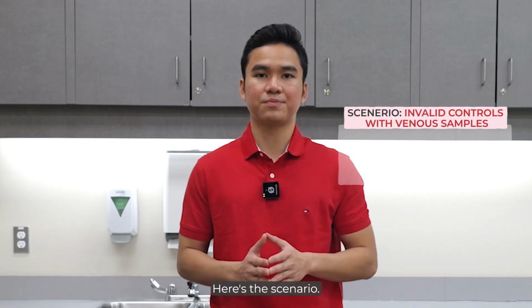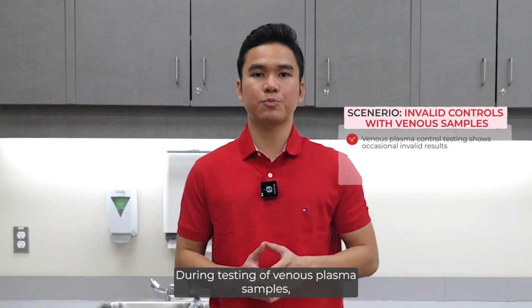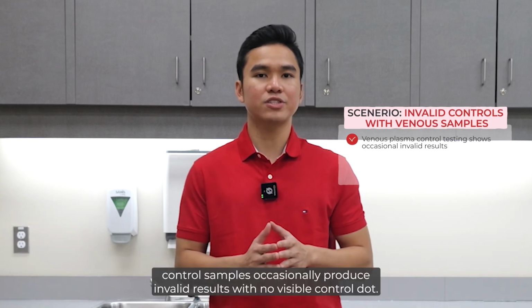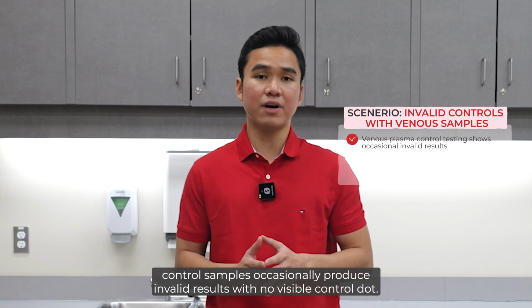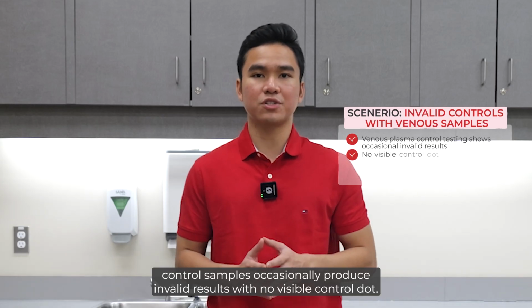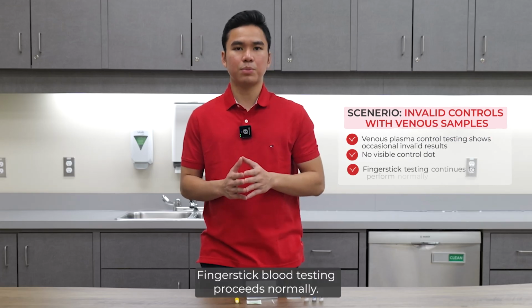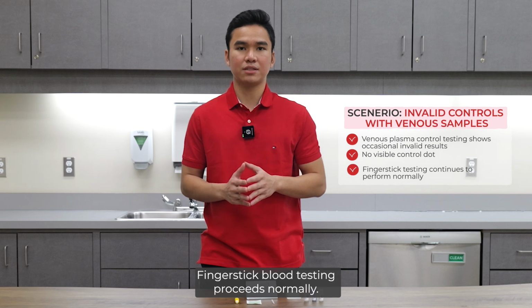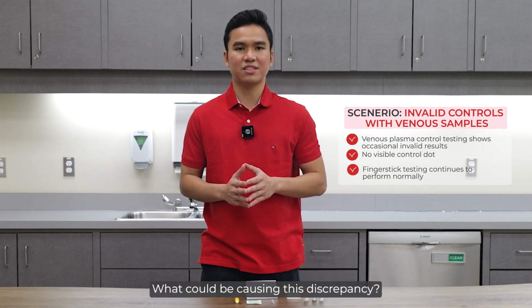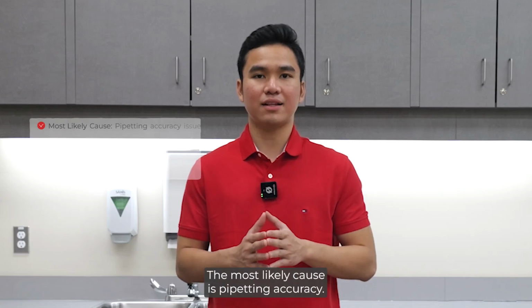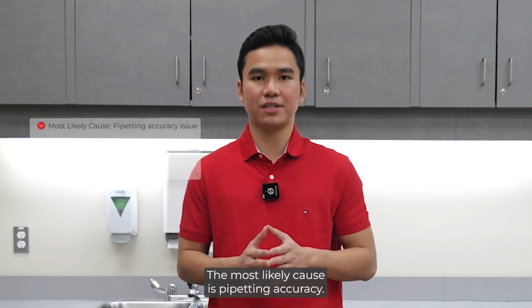Here's a scenario. During testing of venous plasma samples, control samples occasionally produce invalid results with no visible control dot. Fingerstick blood testing proceeds normally. What could be causing this discrepancy? The most likely cause is pipetting accuracy.